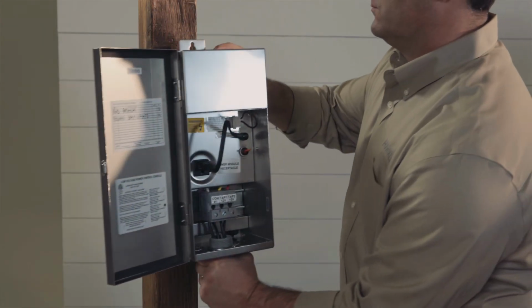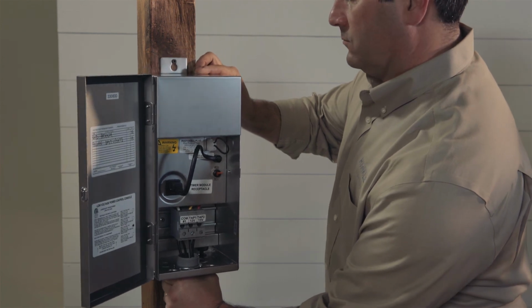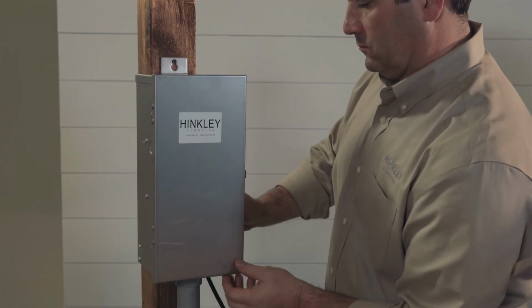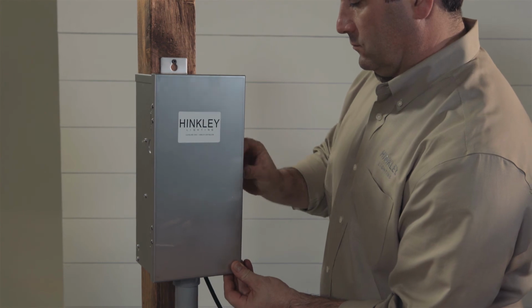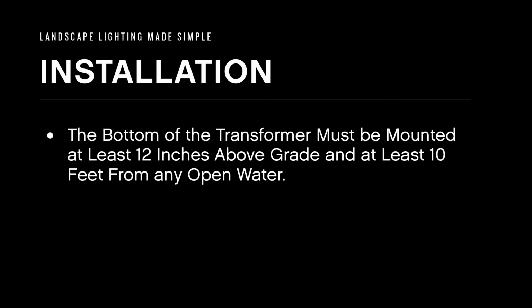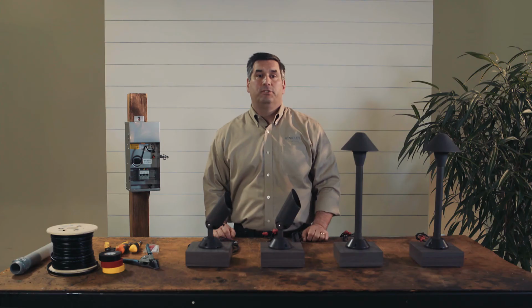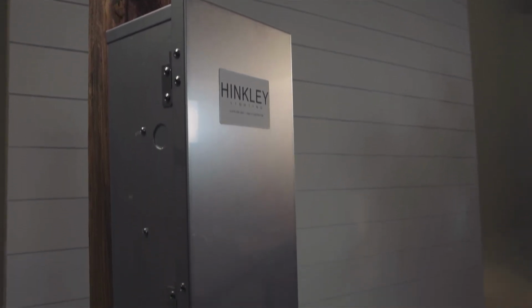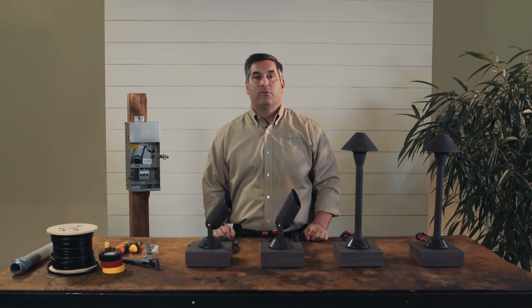Once the main cable run is securely attached to the transformer, you can mount your transformer to the structure or use a secured post. The bottom of the transformer must be mounted at least 12 inches above grade and at least 10 feet from any open water. A post is usually the preferred method to mount the transformer. Using a post may allow you to mount and position the transformer out of the line of sight. Use discretion when mounting on a front or back porch. Most homeowners will not want the transformer mounted in plain view.